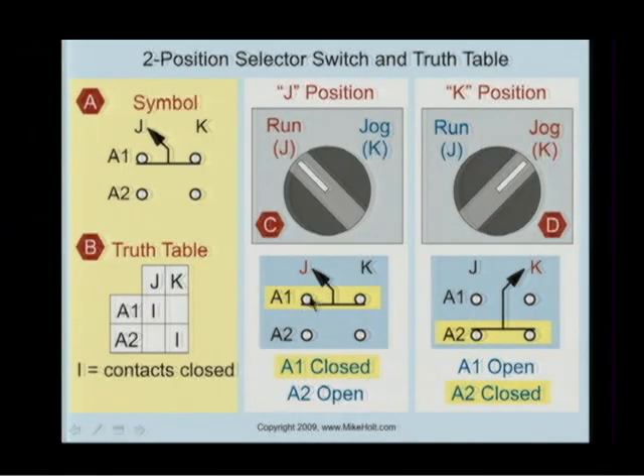Under the J position, A1 contacts are closed. And that's a number 1. What the number 1 means is true. Are these contacts closed? And the answer is yes. Or you could put a check mark there saying the contacts are closed. Now, it doesn't have to be a J and a K. It could be whatever. It could be a 1 and a 2. It could be whatever the selector switch is identified as, and they'll give you a truth table with it so you know, okay, under this condition, these A1 contacts are closed.